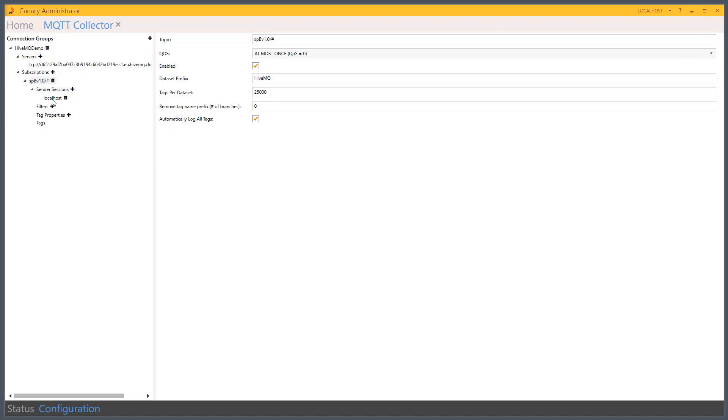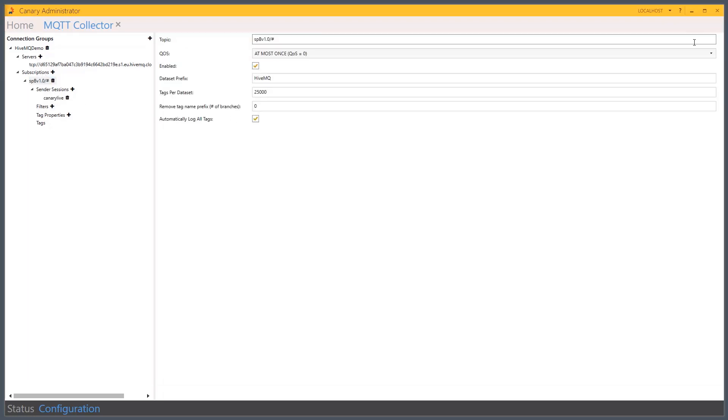Last, I tell it where the historian is located. By default, it's looking to the localhost. If you have the MQTT collector installed local to the historian, you would leave it as localhost. In my instance, I'll be sending to a different historian. And that will be my historian machine name called CanaryLive. Now I could also here put in the IP address. I don't need to do that based on my current configuration. We'll apply those changes.